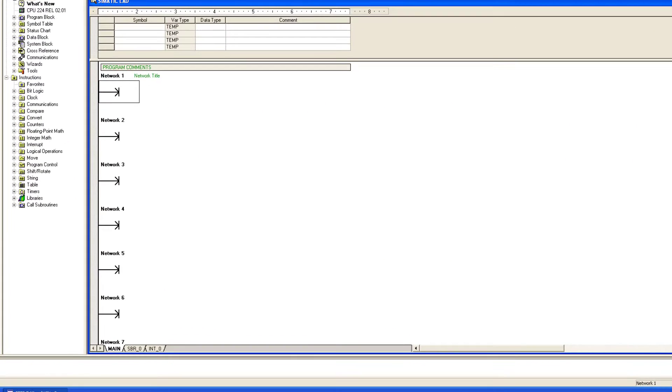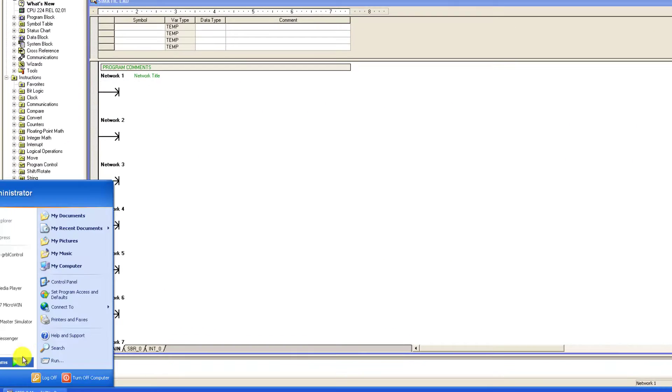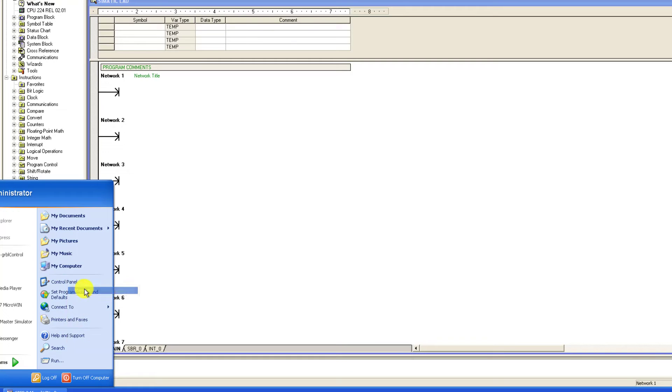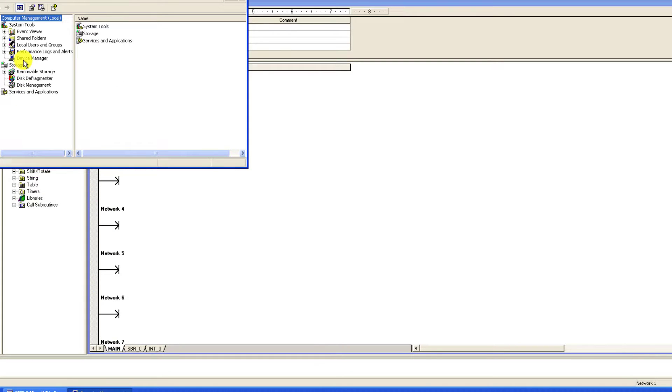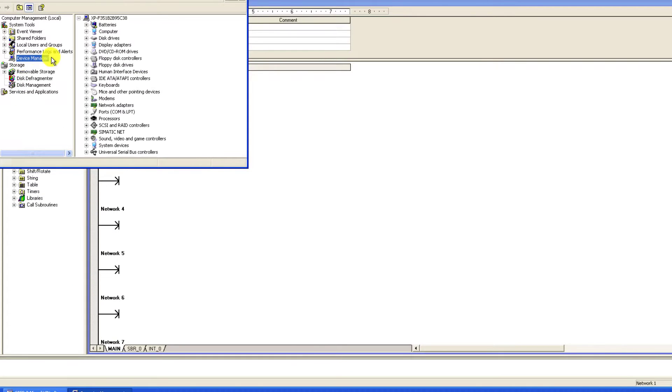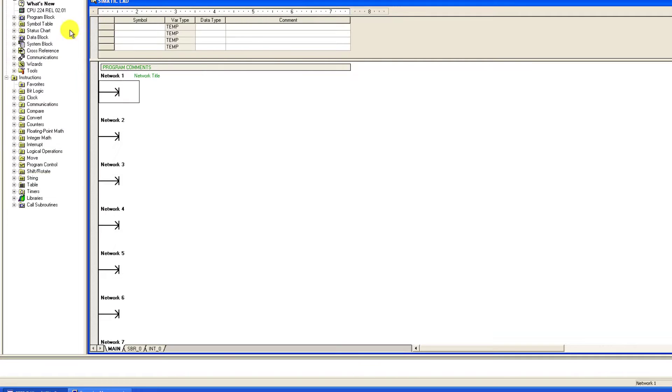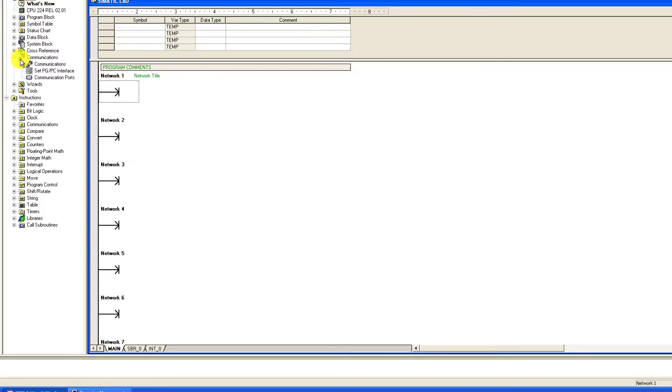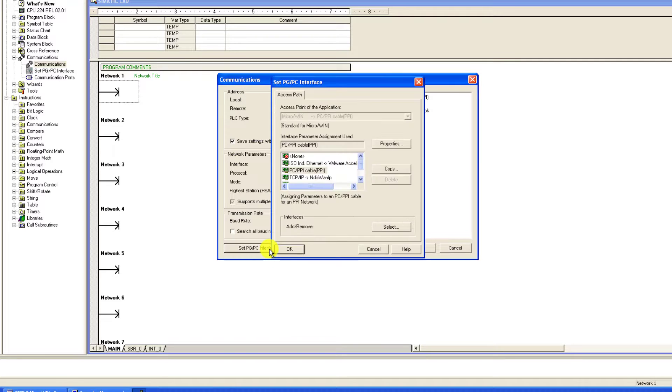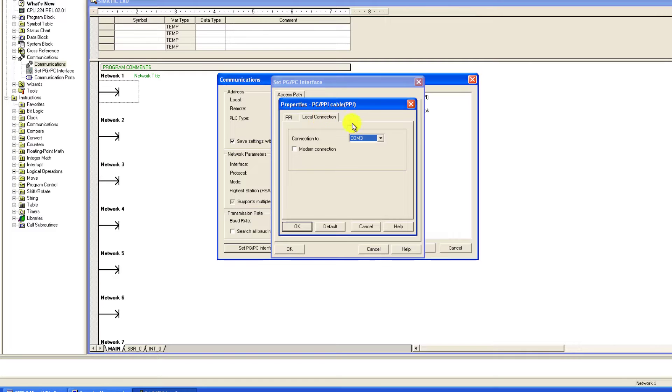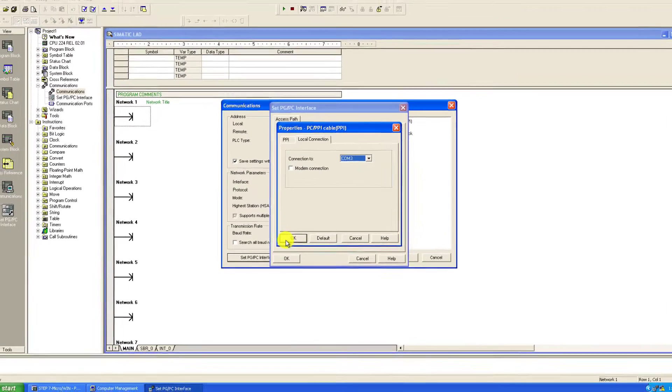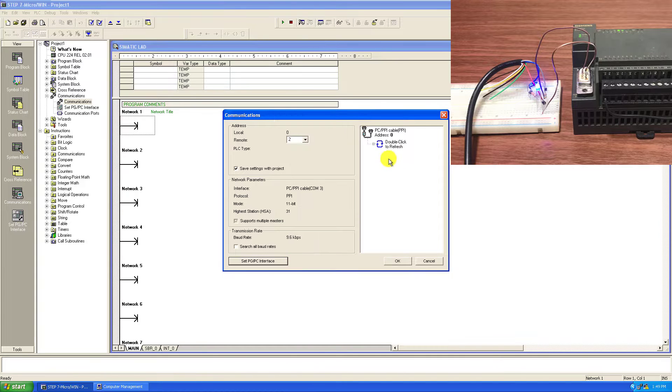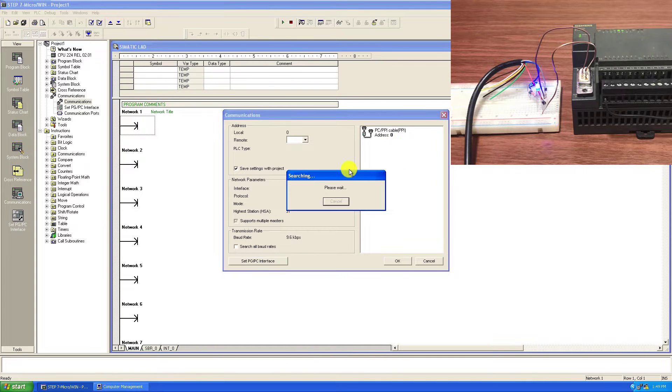I will go to start on the software, and then go to my computer manager and then device manager. We need to confirm the COM port. And we can see that our programmer is connected on COM3. I will go to communication, double click on communication. Go to set PGPC interface, and then properties, and then local connection. And then we can confirm our COM port, that is COM3. I click okay. And now double click on this icon to search for the PLC.